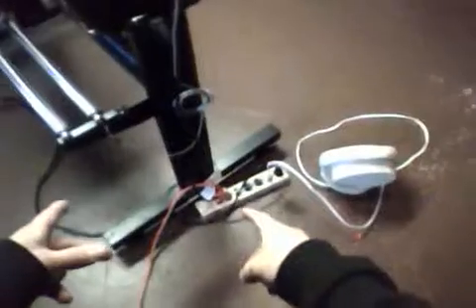What I did was run this wire all the way across my basement straight to the ground for the house — the grounding rods that are actually in the ground. You can see right here my wire comes in and it's connected directly to the house ground. Once I did this, I had total relief — I wasn't having nearly as many issues.